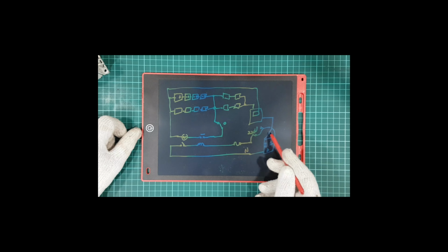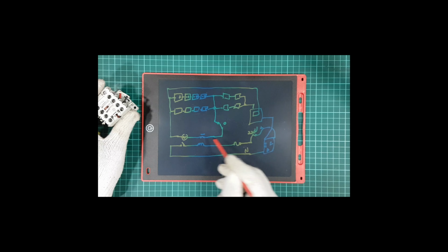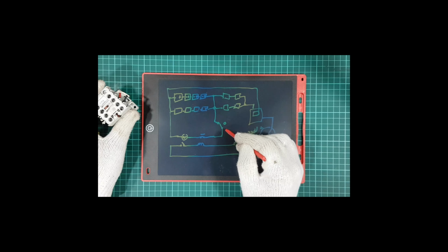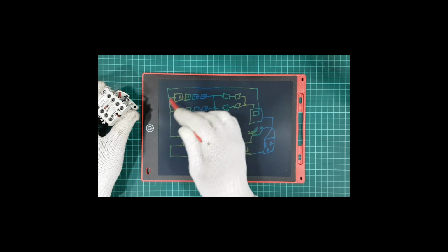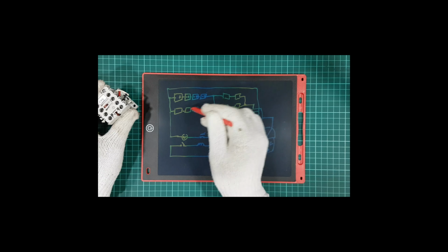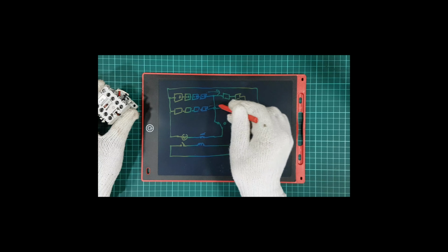It will allow the 220 volt supply to flow through the circuits, which will activate this unit. This will close, and the power from the solar panels will then heat up the geyser. Once the geyser is hot, this will open up again. It will cut the power here.